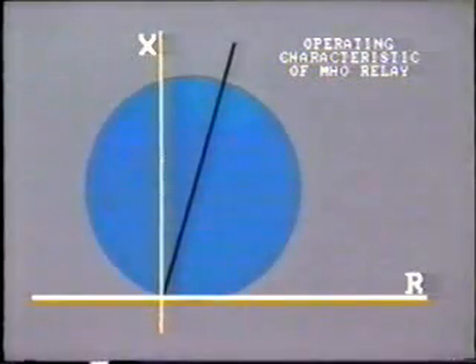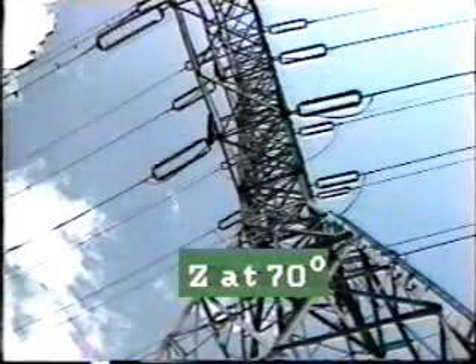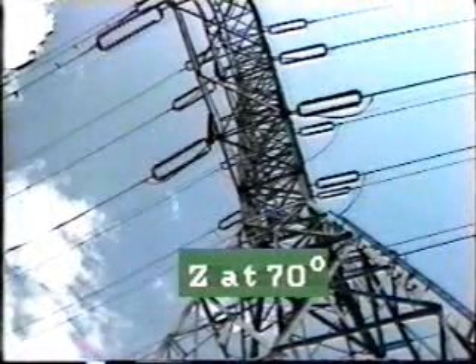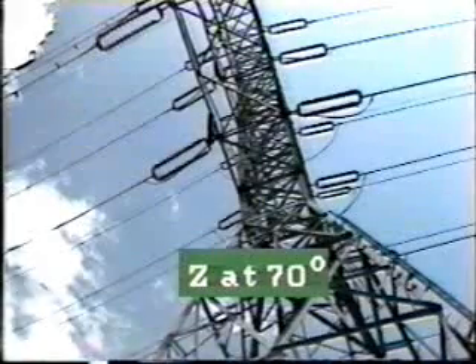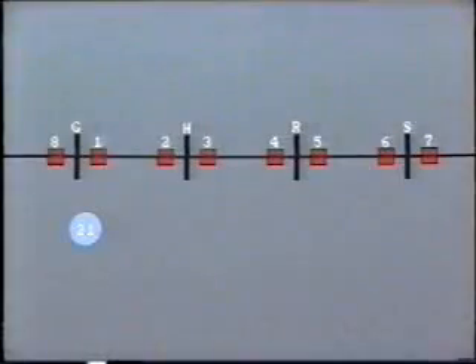Another important point is that the relay trip point is at a higher impedance when its phase angle is at this point, 70 degrees, than for a position, say, here, when the impedance angle is only 20 degrees. This is not coincidental. The 70-degree angle approximates the relationship between reactance and resistance of a high-voltage transmission line. With a short circuit occurring on the transmission line, all of the impedance would be represented by the line impedance, that is, at an angle of about 70 degrees.